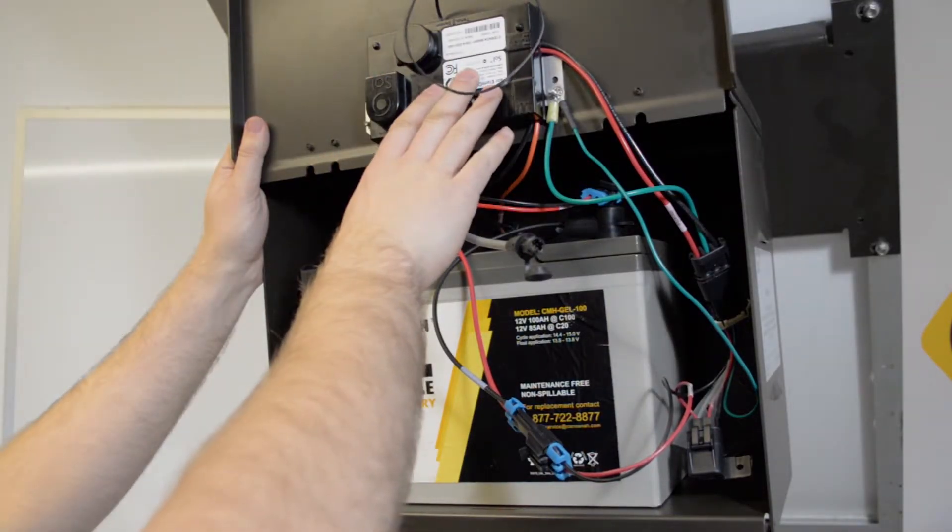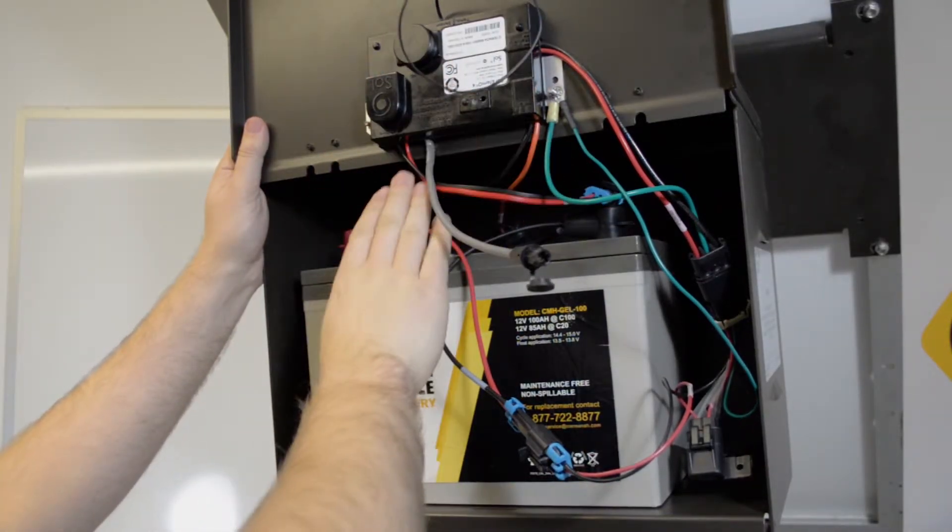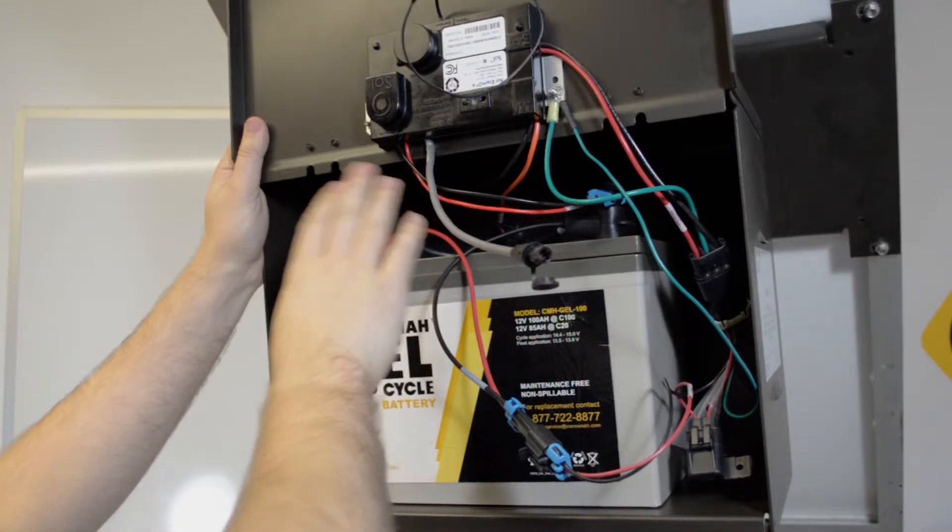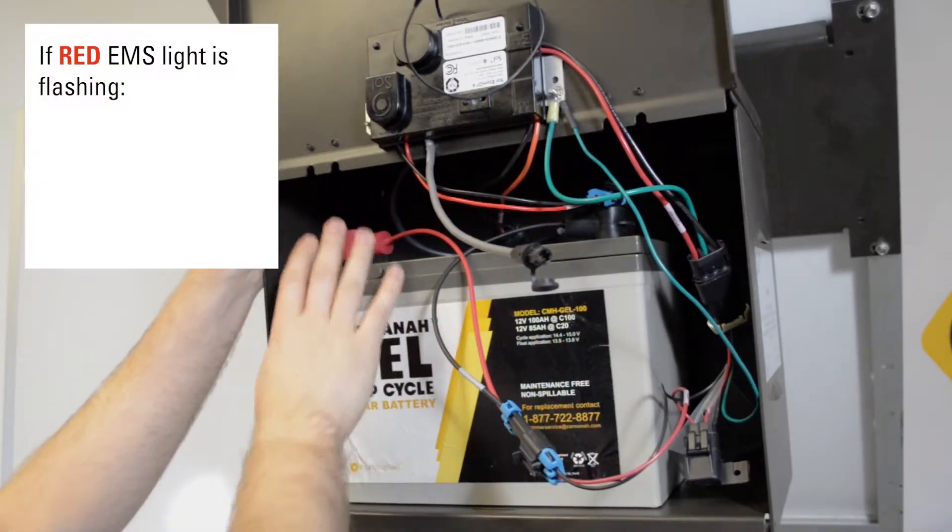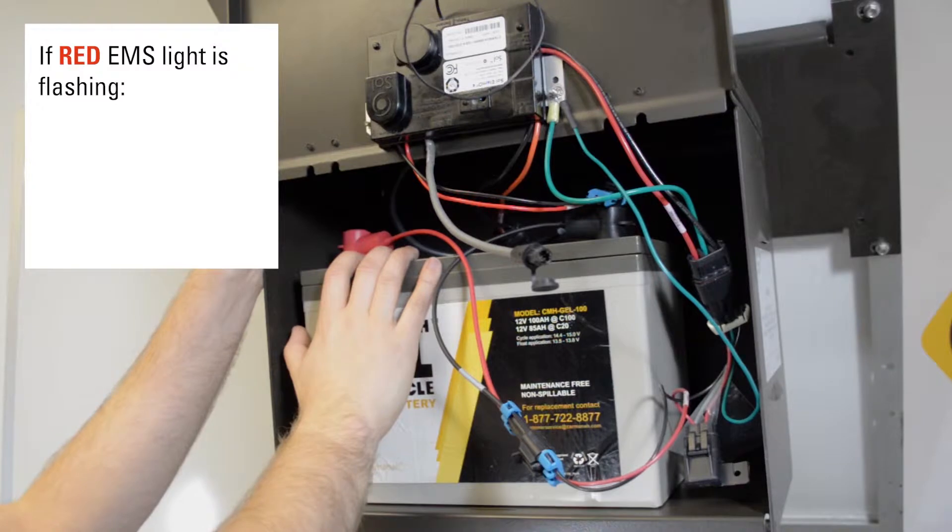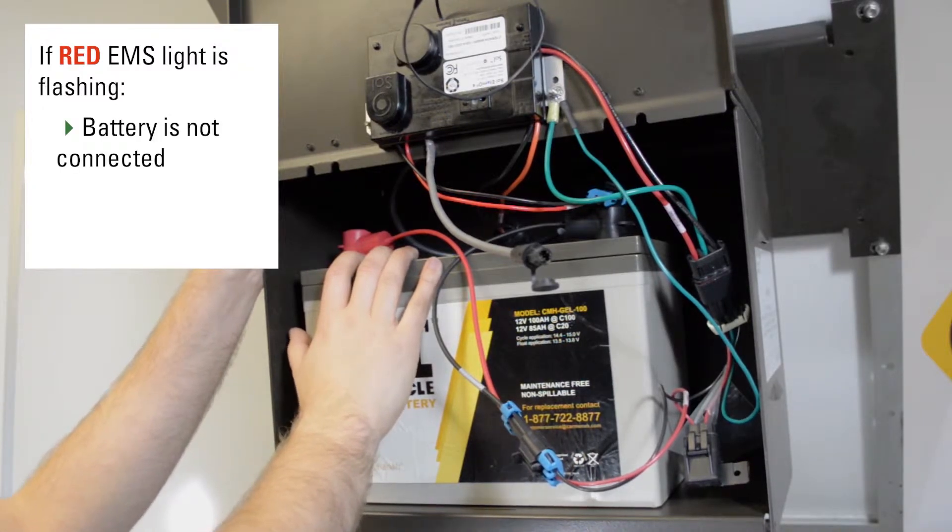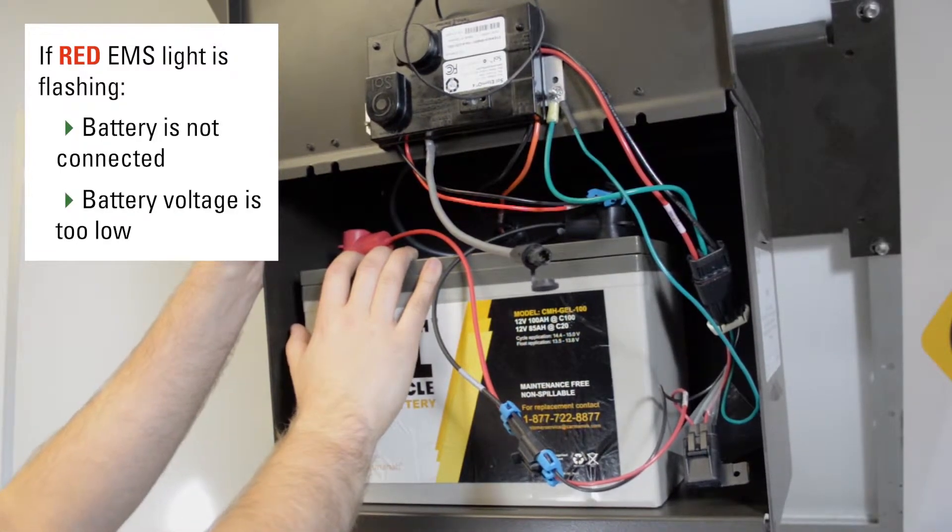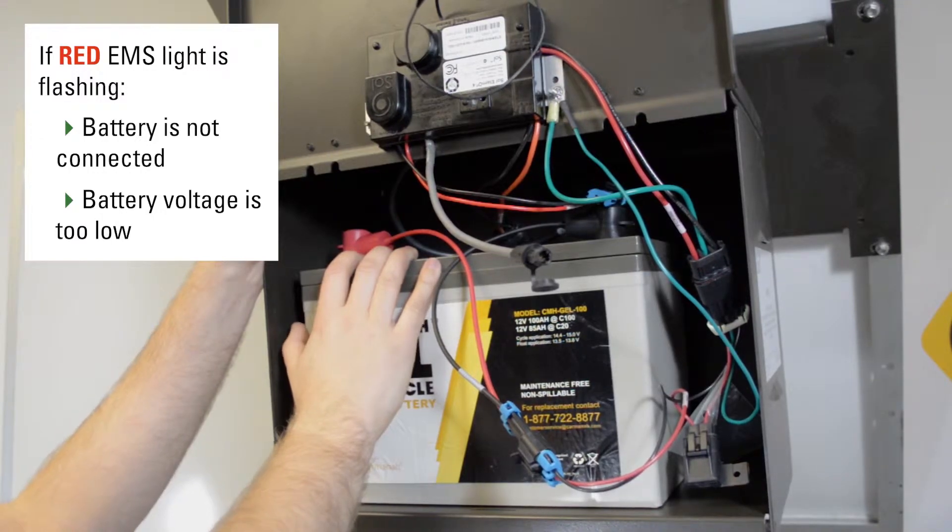So assuming you have a working EMS with the panels connected and the fixture operational, the focus is shifted to the batteries. If the red light seems to be flashing, that indicates that either the battery is disconnected or the voltage of the battery is far below what is expected and may need to be replaced.